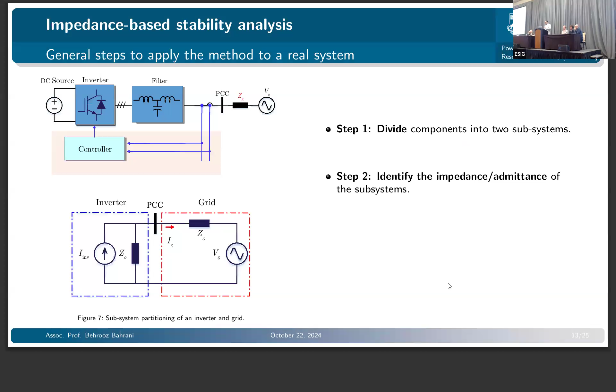This is one example where we identified the impedance of two inverters, and benchmarked them against their analytical model to make sure it is very accurate, and the procedure is accurate. Then we applied Nyquist stability criteria and changed the SCR of the grid, going from 2 to 5. We realized that when going from 3 to 2.5, we are encircling the critical point, meaning the system is expected to be unstable.